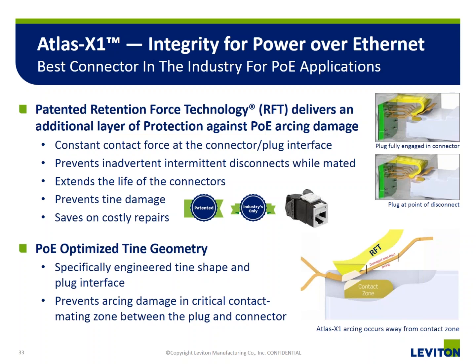There's quite a bit of communication that goes on in that short time span when a powered device is first connected. The problem is that when you take the patch cord and disconnect it, there's no way to have that conversation, because the source and the device don't know when they're going to be disconnected. So every time you remove a patch cord from a PoE device, it's a disconnect under load. The problem you can run into is that over time you can have some sparks, some arcing, and that could damage the tines and the spades on the patch cord plug.